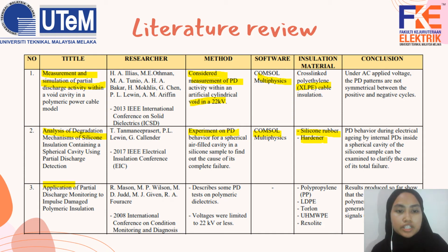Thirdly, about the application of partial discharge monitoring to impulse damaged polymeric insulation. The method used by this article is that they describe some PD tests. They do the experiment, and the voltage is limited to 22 kilovolt or less. So they don't use software since they use an experiment. The insulation materials in this article are polypropylene, LDPE, Torlon, UHMWPE, and Rexolite.